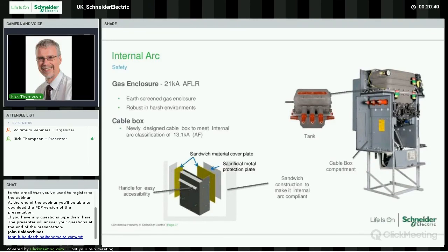That fault could be one of many things, but we still have to test all our switchgear before we put them onto the market. And within RN2D, there are two areas which need to be tested. First one is the gas enclosure. If there was an internal arc inside the gas enclosure, then we've got to test it for the design. In this case, we tested it for a fault level of 21 kA.